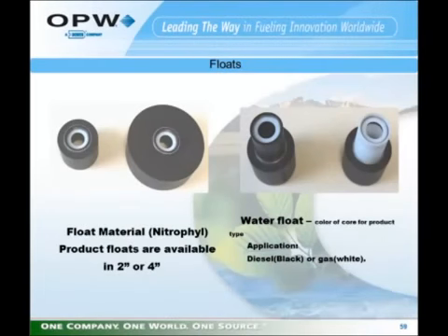The standard float material is a Nitrophyl material. Product floats were available in 2-inch and 4-inch. They are now only available in the 2-inch. We no longer furnish a 4-inch product float. The water float is a 2-inch water float that has a white neck for gasoline and a black neck for diesel. There is no neck on the product float.